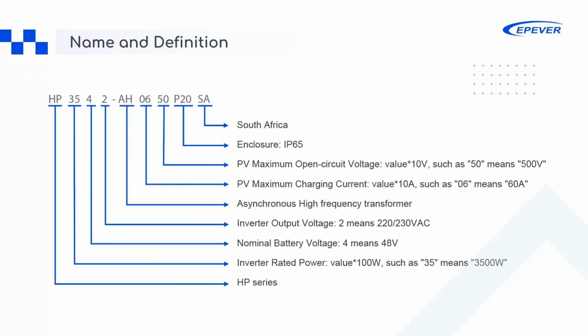Let's break down the naming convention. HP at the beginning stands for high power, indicating this inverter charger is designed for high power applications. Next is 35, representing the inverter's rated power in hundreds of watts, so 35 means 3,500 watts. The digit 4 indicates the nominal battery voltage, meaning the device operates at 48 volts. The digit 2 denotes the inverter output voltage, meaning 220-230. Then the letters AH stand for asynchronous high frequency transformer, which we'll explain in this webinar.